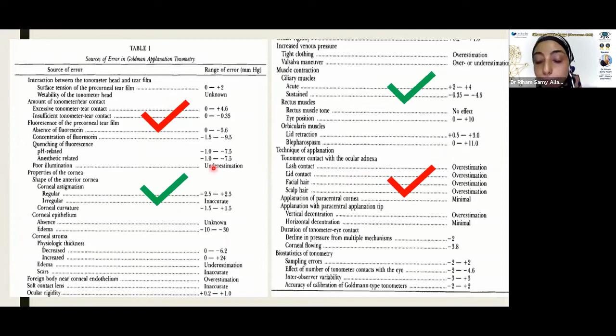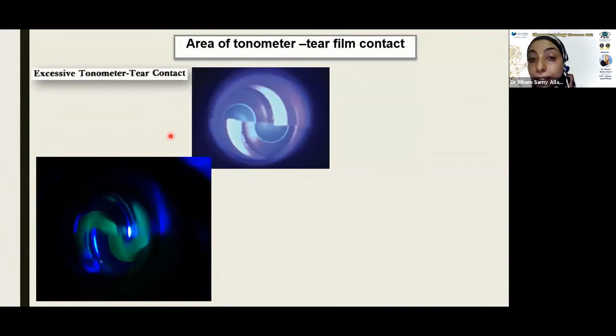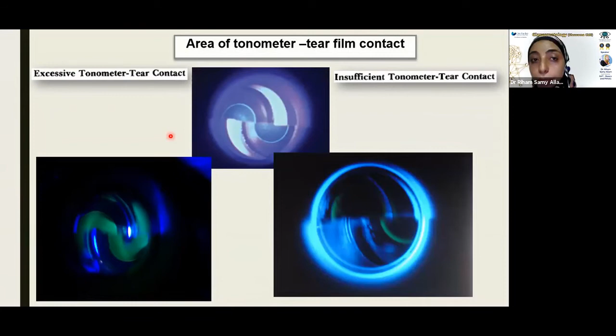One of the sources of these errors is the area of tonometer tear film contact. We have the tear film meniscus and the applanation tip or the probe just touching the anterior surface of the cornea. In order to obtain these well-defined, adequate marks, we have to have an area of contact which is not too excessive, for example when we have a tearing patient or excessive fluorescein, because this leads to overestimation of the pressure. Or we don't want insufficient tonometer tear contact, with which the fluorescein will not be very apparent, and so we will get an underestimation of the intraocular pressure.